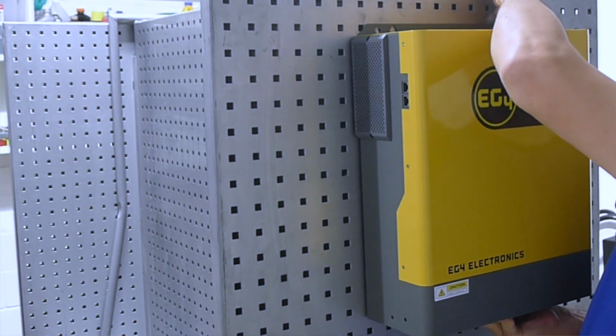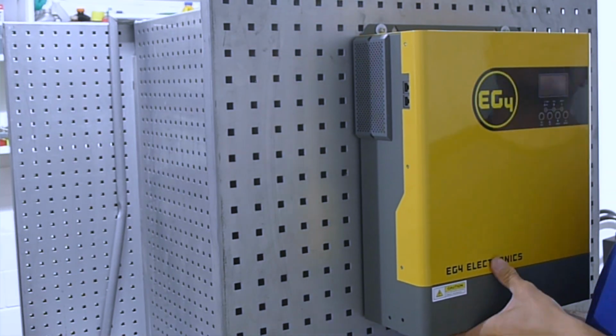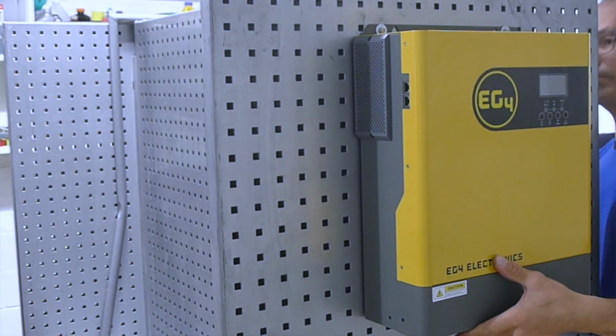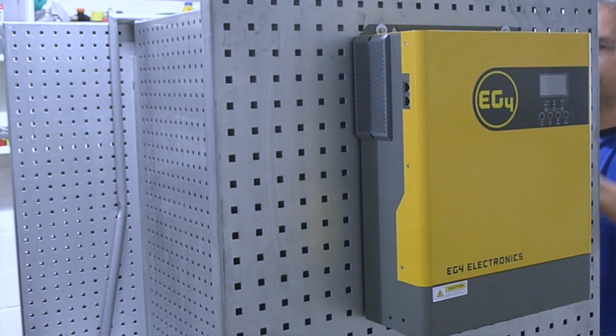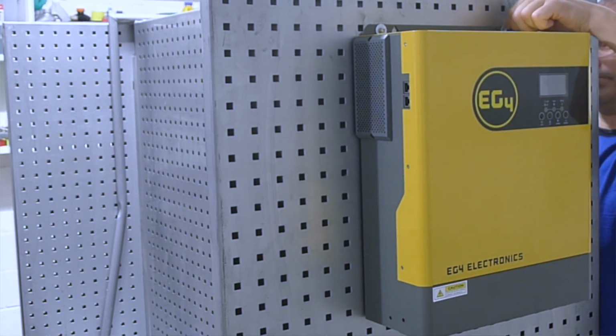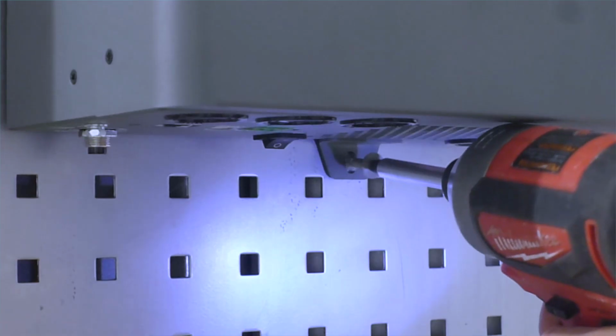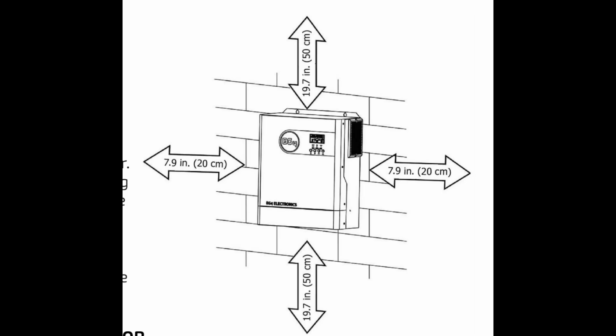First, let's secure the inverter to the top section of this panel. We can mount the inverter on any non-combustible material vertically that is strong enough to bear the weight of the inverter. Be sure to keep other objects and surfaces at a distance of 19.7 inches up and down, and 7.9 inches on the sides.